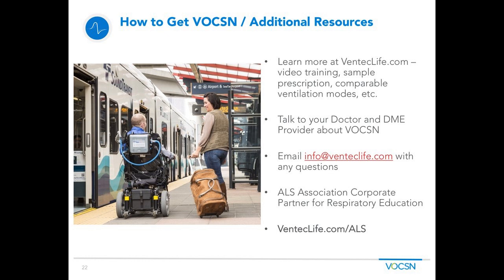But it does not require a proprietary circuit? It does require the Ventec One circuit. This circuit is the only one that can do multiple therapies with one circuit. As much as we'd like to not be making circuits, much of the integration capability of VOCSN is tied into the circuit. So you do have to use the Ventec One circuit, whether that's active, passive, with oxygen, or with heat. Generally you'll find that circuit to be about the same cost as what you're paying today, and it will last as long, if not longer, than your traditional circuit.